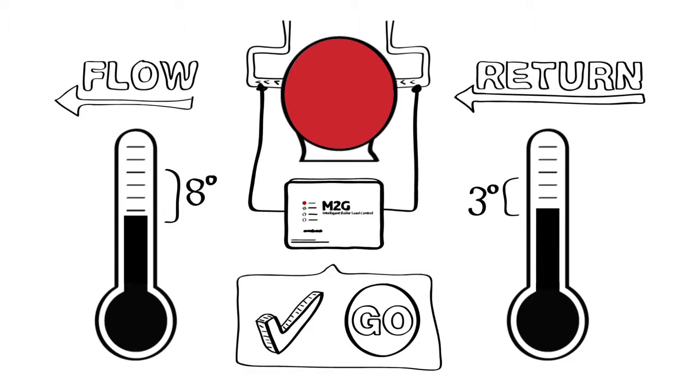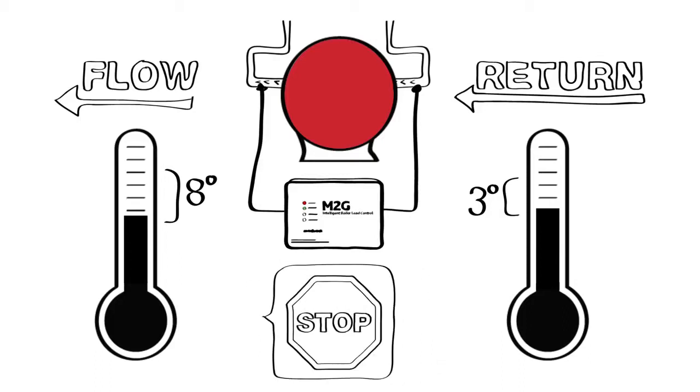the M2G recognizes this as natural heat loss and not a real demand. It won't allow the boiler to fire unless the flow drops 8 degrees or the return drops 3 degrees below the initial snapshot reading. The maximum period M2G can prevent the boiler firing is 15 minutes.